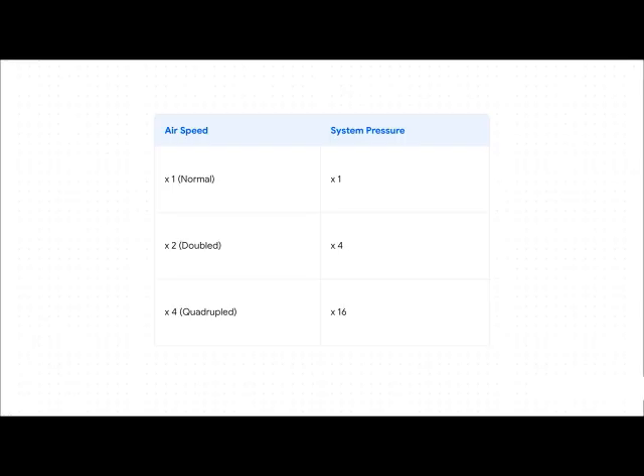Take a look at these numbers, because this is where things get a little nuts. If you double the speed of the air, the resistance doesn't just double, it quadruples. What if you quadruple the speed? The pressure goes through the roof by a factor of 16. But here's the real kicker: to overcome that quadrupled pressure, the fan has to use 8 times the power. Let that sink in, 8 times.